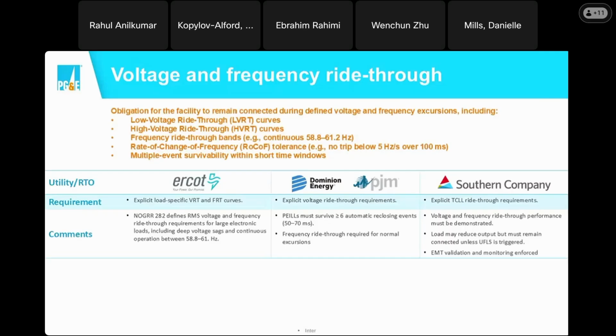Another component, if you think back to the Dominion event, is that there's multiple event survivability required within short windows. What that means is you need to be able to ride through at least 6 automatic reclosing actions, or 3 automatic reclosing actions, based on the local utility's reclosing practices.